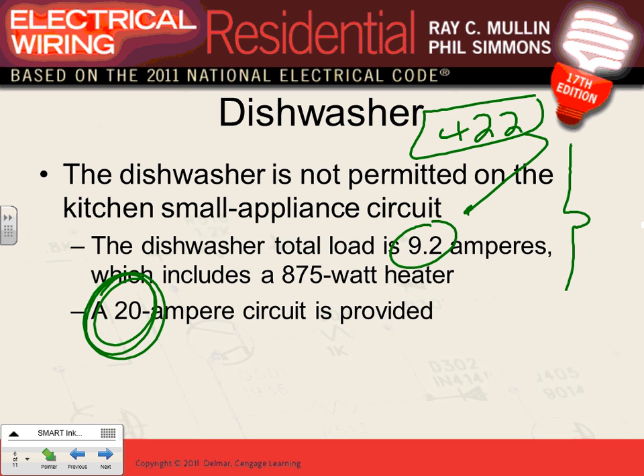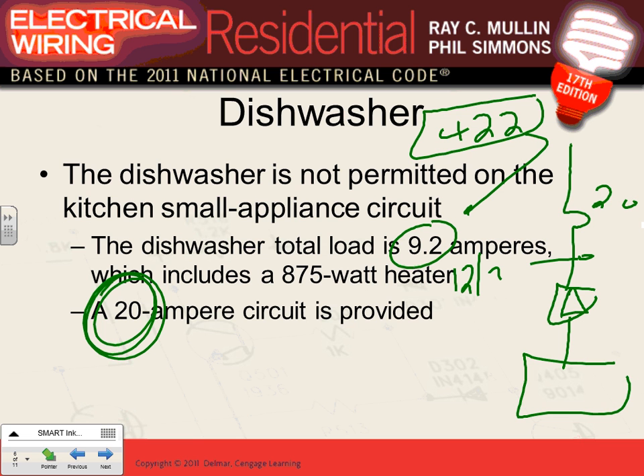You came up with a 20 amp circuit here, and your conductors will be 12-2, and you have a plug in here. You plug it in and you tie the machine. So here's what. In this case, I have my overcurrent protection device, I have my conductor, and I have my disconnect.